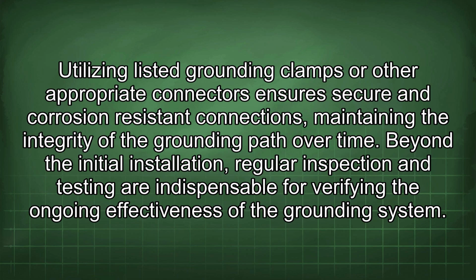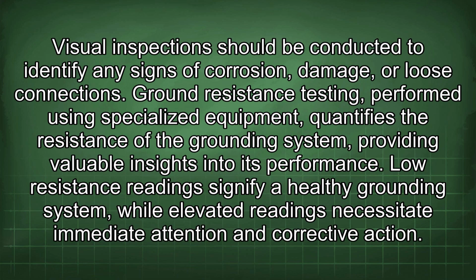Utilizing listed grounding clamps or other appropriate connectors ensures secure and corrosion-resistant connections, maintaining the integrity of the grounding path over time. Beyond the initial installation, regular inspection and testing are indispensable for verifying the ongoing effectiveness of the grounding system. Visual inspection should be conducted to identify any signs of corrosion, damage, or loose connections. Ground resistance testing, performed using specialized equipment, quantifies the resistance of the grounding system, providing valuable insights into its performance. Low resistance readings signify a healthy grounding system, while elevated readings necessitate immediate attention and corrective action.